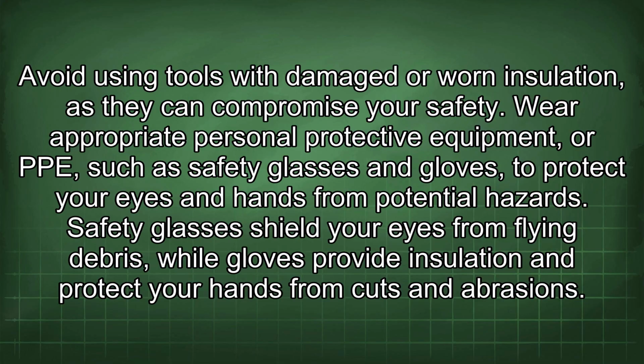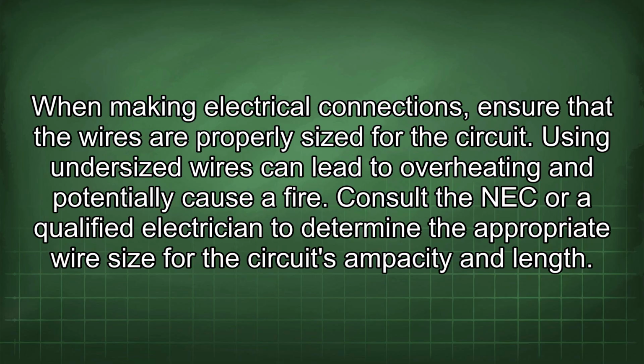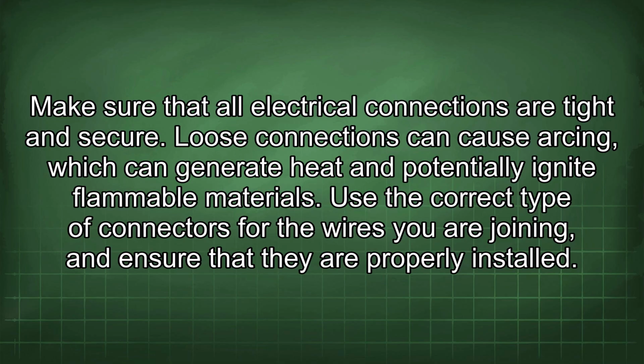When making electrical connections, ensure that the wires are properly sized for the circuit. Using undersized wires can lead to overheating and potentially cause a fire. Consult the NEC or a qualified electrician to determine the appropriate wire size for the circuit's ampacity and length. Make sure that all electrical connections are tight and secure. Loose connections can cause arcing, which can generate heat and potentially ignite flammable materials. Use the correct type of connectors for the wires you are joining and ensure that they are properly installed.